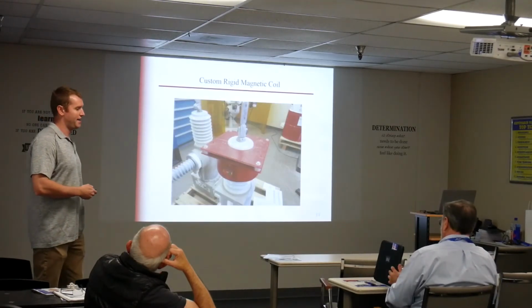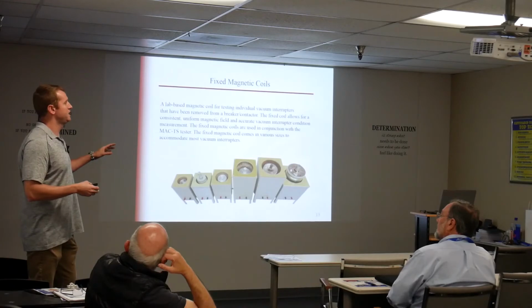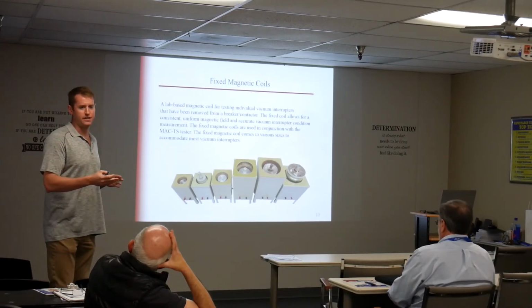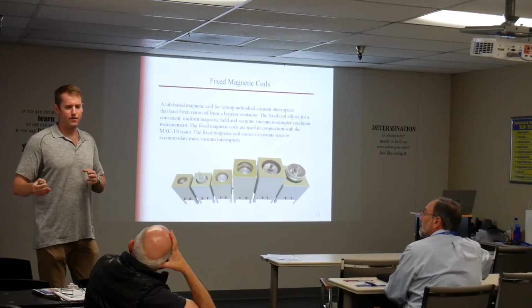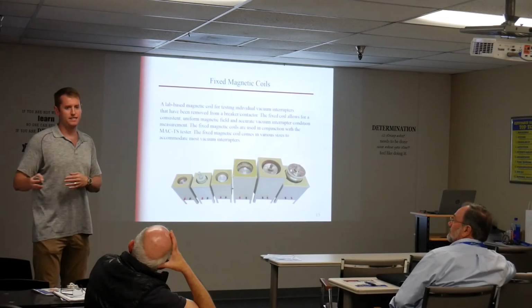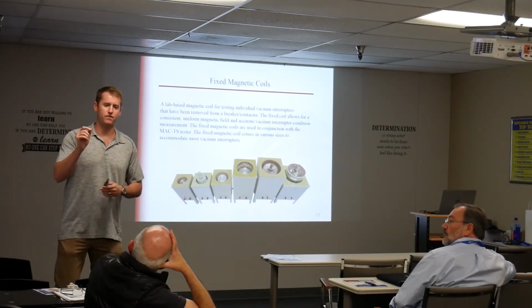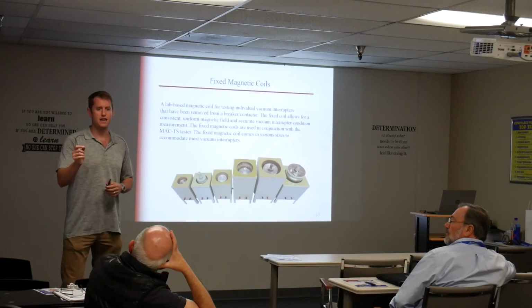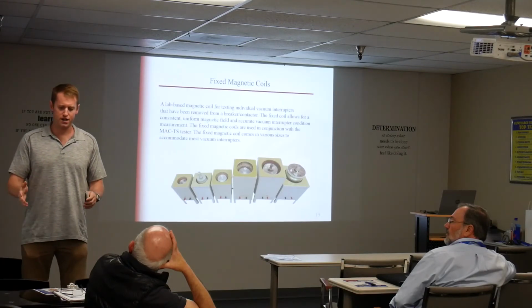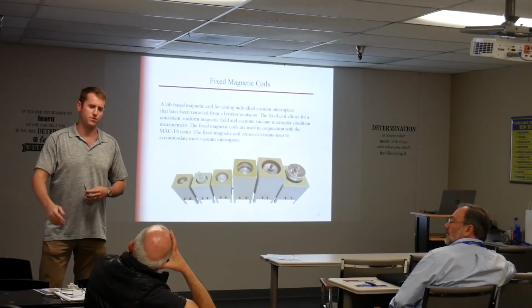They don't like that's the other thing about these interrupters. A lot of times they sit in a warehouse for 10 years, and then they get bought in surplus, and then they get stuck in breakers. With Westinghouse, the first 2 digits of their serial number is the age, and I've tested a Westinghouse breaker that was 10 years newer than the bottles that were installed in it.